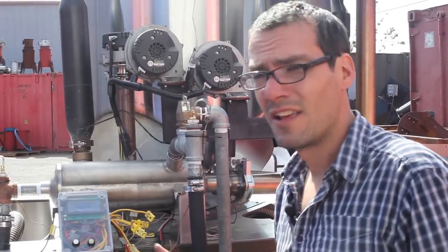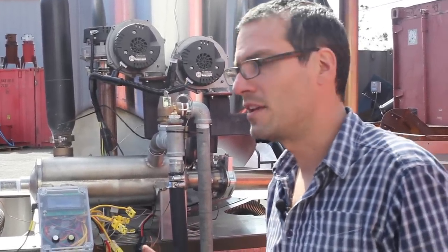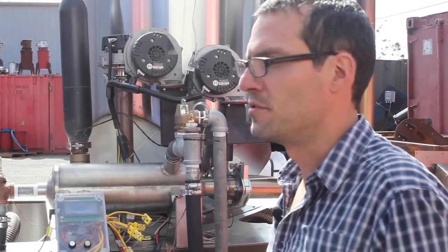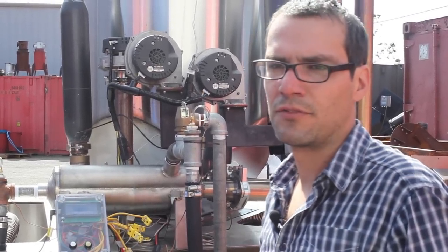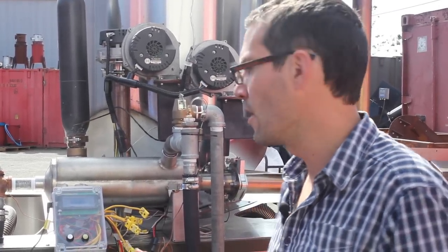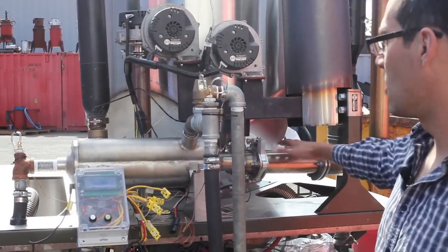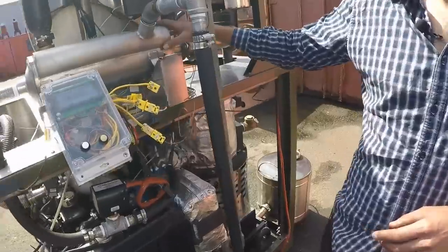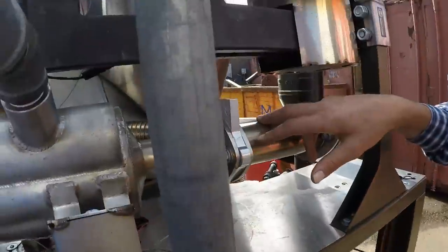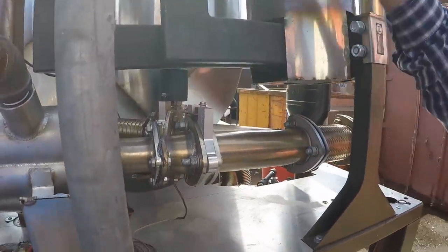If we have high return temperatures to the CHP system because there's not enough heat being dumped where the hot water is being used, say in a warehouse or in crop drying or something, then we have an exhaust gas bypass valve. So we bypass the shell and tube heat exchanger and send the exhaust gas straight out.